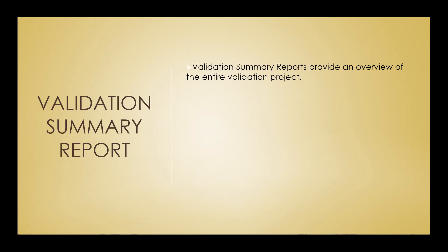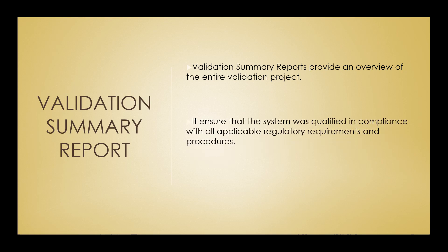Let's understand what is a validation summary report. A validation summary report is a report where you capture all the details of performed validation activities, such as the deliverables you prepared and IQ, OQ, PQ satisfactorily performed, and if any discrepancy is observed, the details of that discrepancy with its resolution. The validation summary report provides an overview of the entire validation project and ensures that the system was qualified in compliance with all applicable regulatory requirements and procedures.